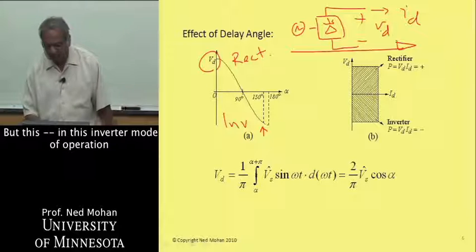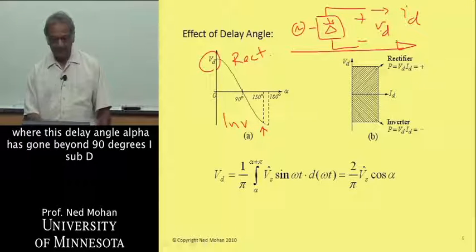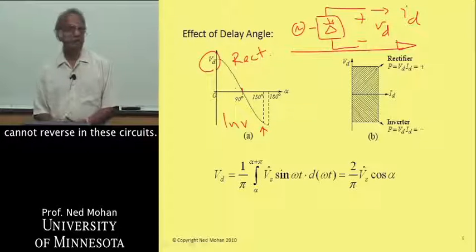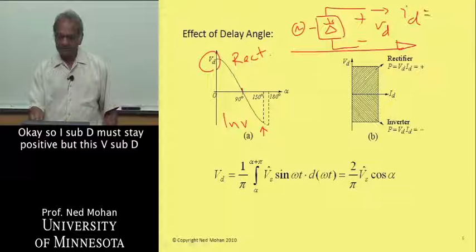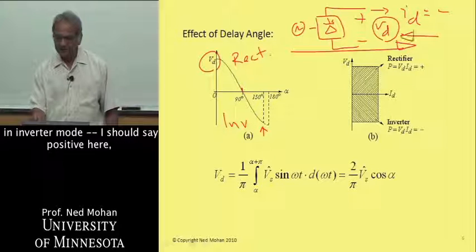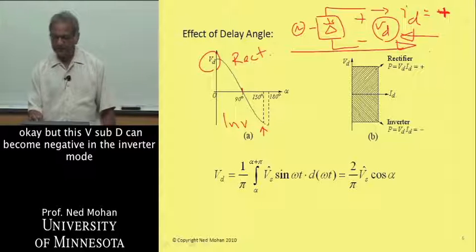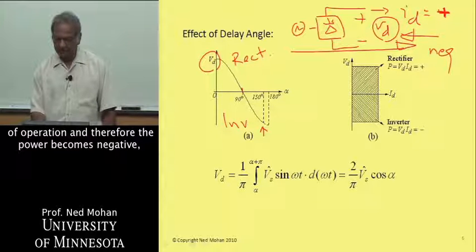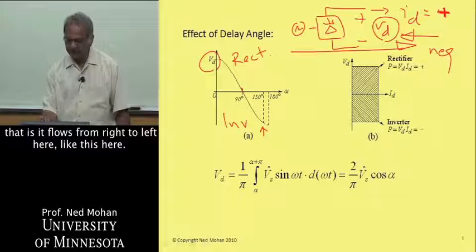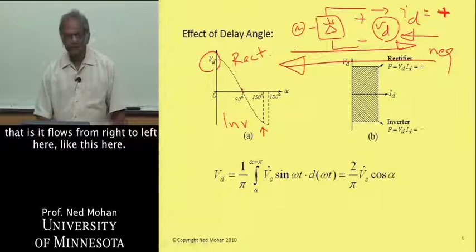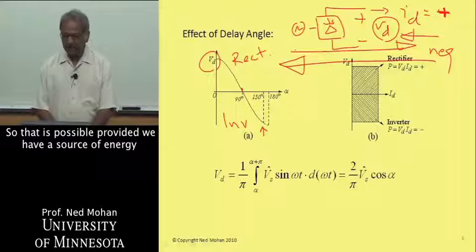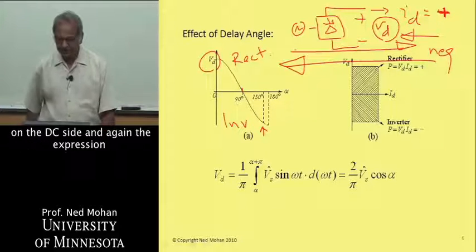But in this inverter mode of operation, where the delay angle alpha has gone beyond 90 degrees, I-sub-D cannot reverse in these circuits. I-sub-D must stay positive, but V-sub-D can become negative in the inverter mode of operation. Therefore, the power becomes negative — that is, it flows from right to left. This is possible provided we have a source of energy on the DC side.